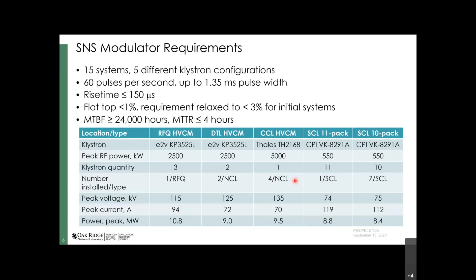Through the drift tube LINAC portion of the machine, we have 4 different klystrons shown here in blue. Those are powered by 2 separate modulators operating at about 125 kilovolts. Through the CCL section, we actually have a 1-to-1 ratio of klystron to modulator, and those operate at about 135 kilovolts.